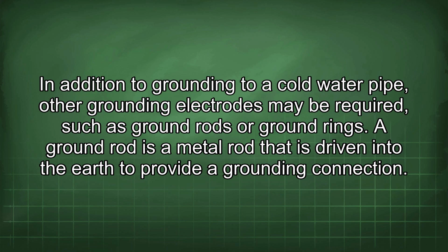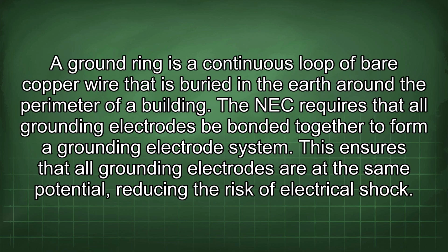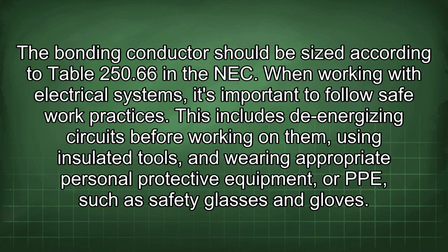In addition to grounding to a cold water pipe, other grounding electrodes may be required, such as ground rods or ground rings. A ground rod is a metal rod that is driven into the earth to provide a grounding connection. A ground ring is a continuous loop of bare copper wire that is buried in the earth around the perimeter of a building. The NEC requires that all grounding electrodes be bonded together to form a grounding electrode system. This ensures that all grounding electrodes are at the same potential, reducing the risk of electrical shock. The bonding conductor should be sized according to Table 250.66 in the NEC.